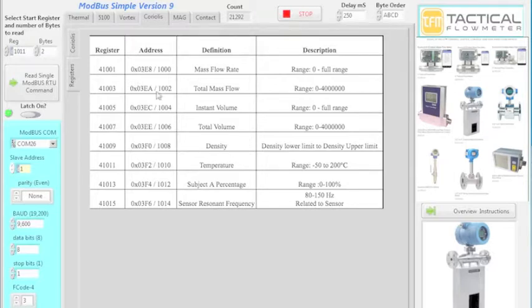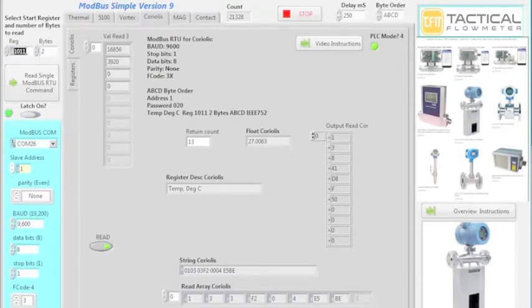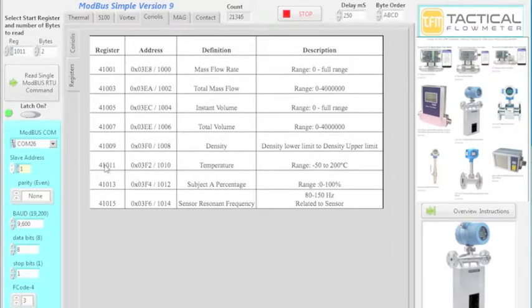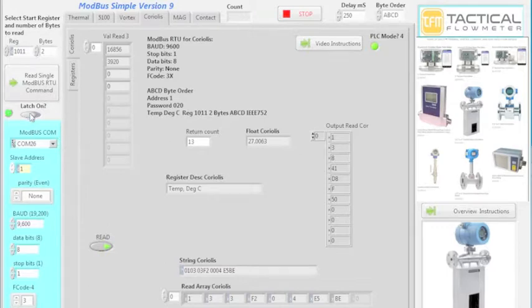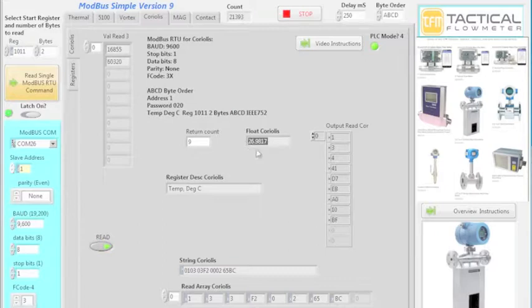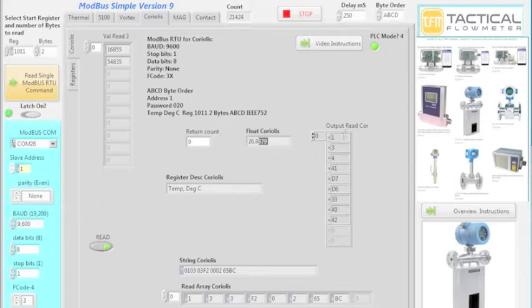If we look at some of the registers — let's read the temperature, which is register 1011. In Modbus RTU, the address 41011 becomes 1011 once we remove the 4. So when I type 1011, I click latch on and we'll see the temperature. Looking at the temperature on the meter — temperature is 26.98. These flickering digits are the LSB of the float in byte order A, B, C, D. This is address 1, FC code 3.